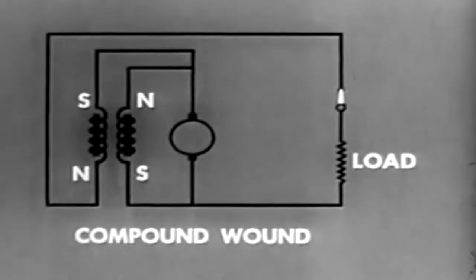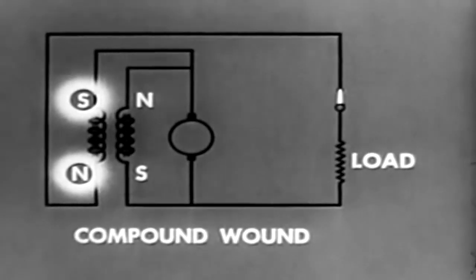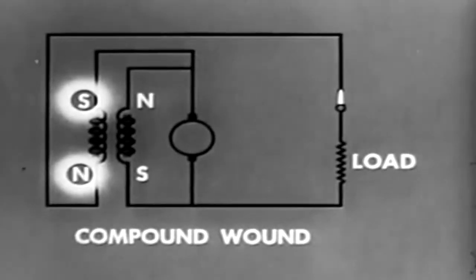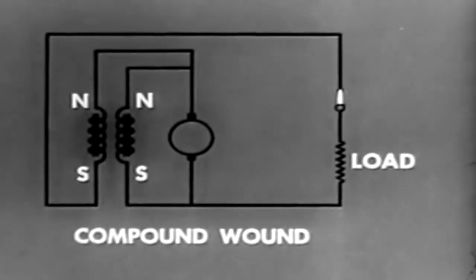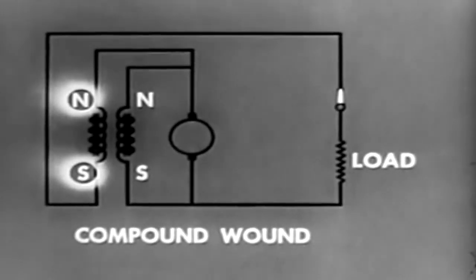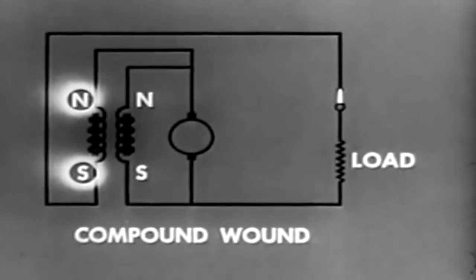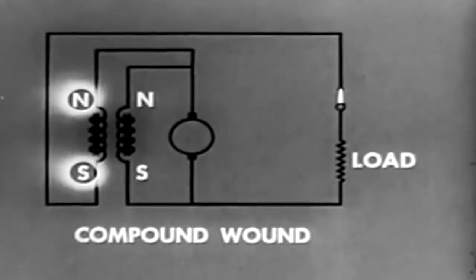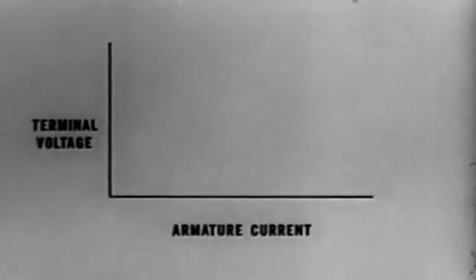When windings are arranged so that magnetic fields oppose each other, it becomes, in effect, a series generator — used only where constant current is the prime requirement, such as in arc welding. By changing the magnetic polarity of one of the fields, the field windings aid one another, and this compound-wound generator has good voltage and fair current regulation. A graphic representation of generator output characteristics shows terminal voltage plotted vertically and armature current horizontally.